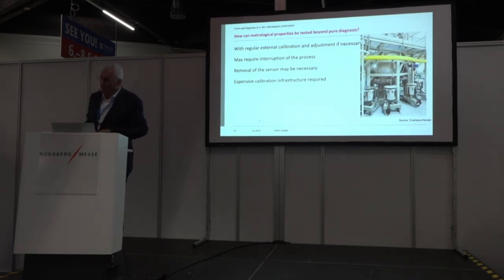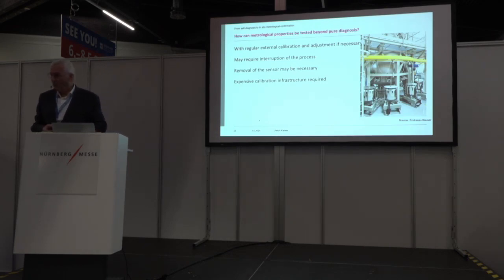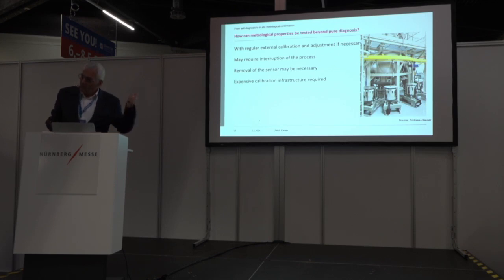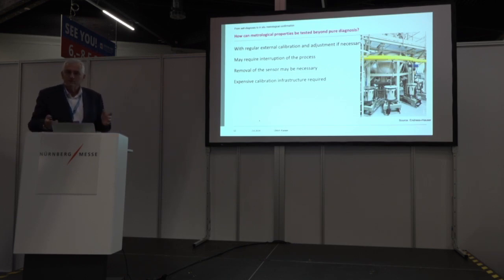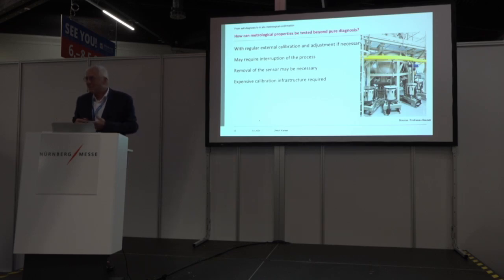This is a calibration infrastructure for calibrating flow measurement devices. It weighs about 10 tons, has a height of 20 meters, and costs 2 million. You cannot bring this to the device - you have to bring the device to this calibration stand, to the calibration infrastructure.